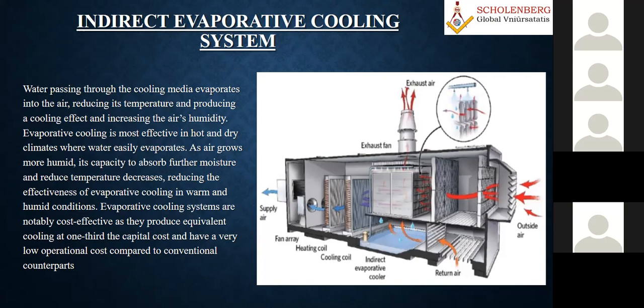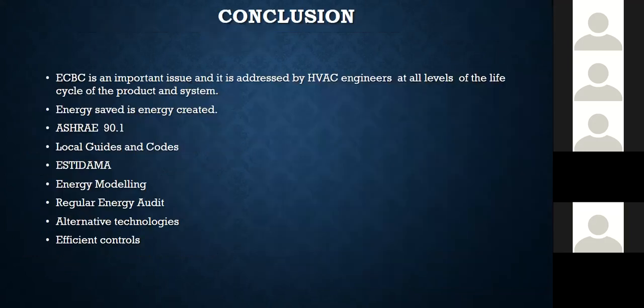But now we have active dehumidification coils. There is a lot of improvement in cooling coil design. Or worst case, we can use chemical dehumidifiers also. This is innovative design, so the sky is the limit. It is the same thing I did in this project, the Oman Museum. It's a dry area, and in many places we have to take 100% fresh air, so we included this type of evaporative cooling system. I know water is very expensive here, but we did an analysis, and because of that my cooling load and capital cost reduced by almost 20 to 30%, and the recurring cost is also included in that.